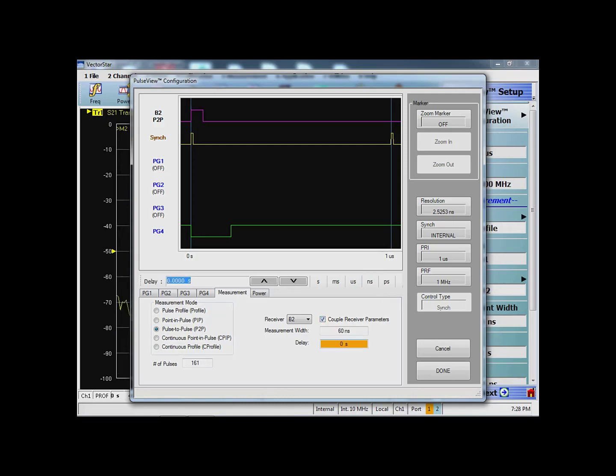And then the delay, because we started at roughly around 160, so a good portion is basically covered. I can do 100 as well because the pulse was pretty stable there. So I do 100 nanosecond. Again, I'm just analyzing. If you see the pink portion, which is the B2 profile, and the green portion of the actual pulse speed that we want to analyze, we have actually covered the main area of the pulse that we want to analyze.